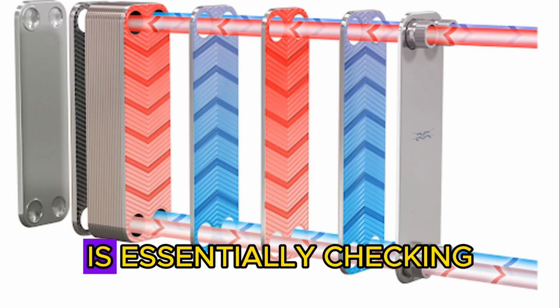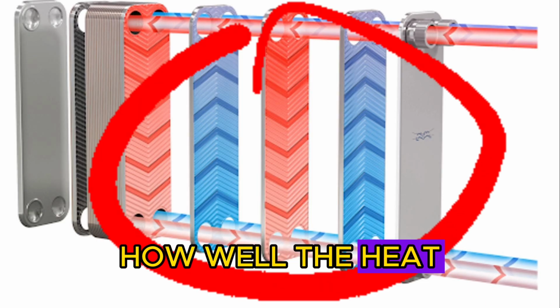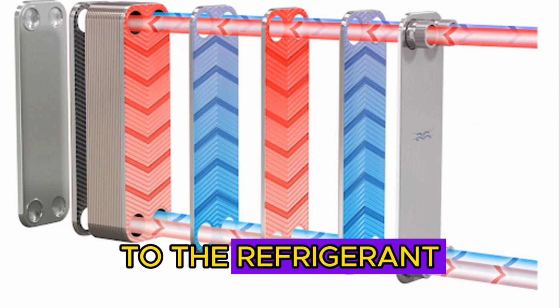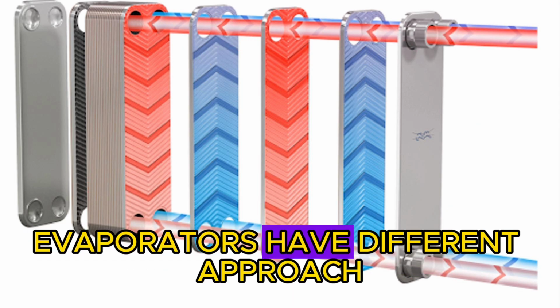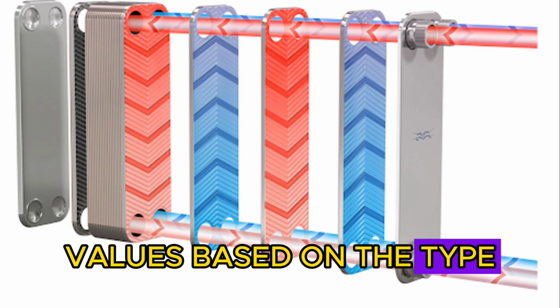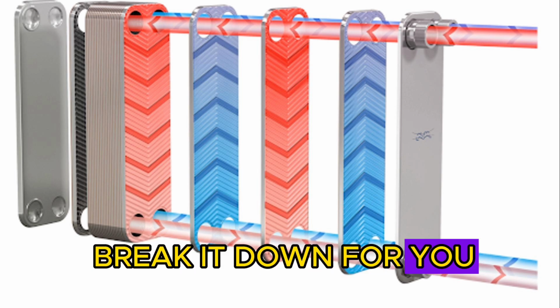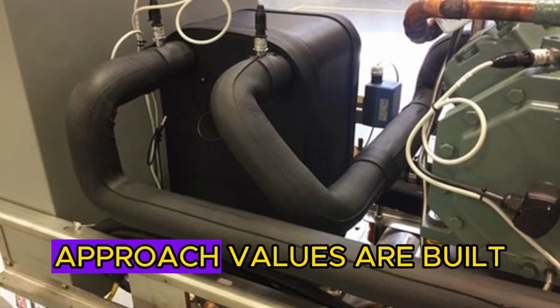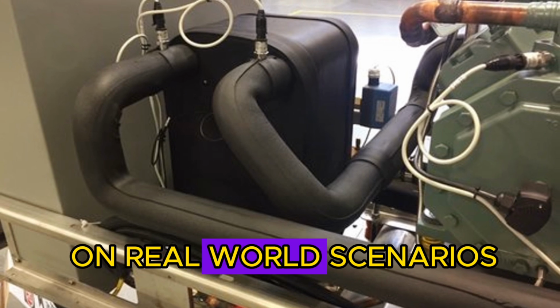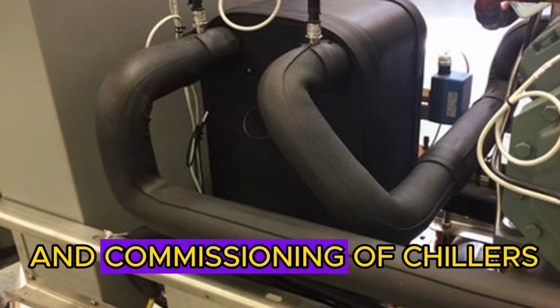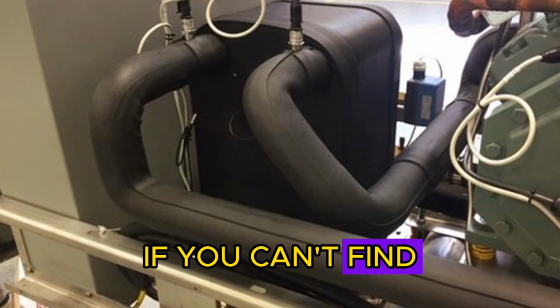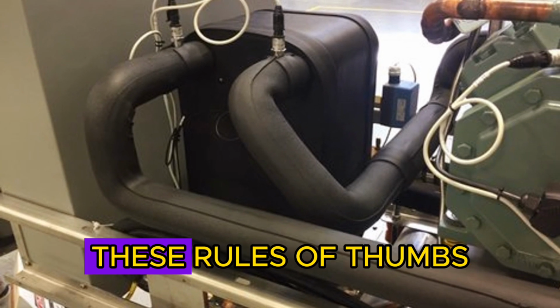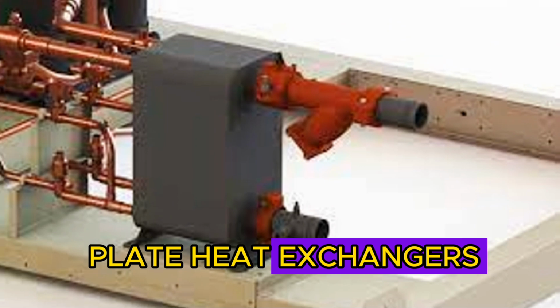What you're doing here is essentially checking how well the heat is transferring from the water to the refrigerant. Evaporators have different approach values based on the type, and we're going to break it down for you. All of the following approach values are built on real-world scenarios at the startup and commissioning of chillers. If you can't find the manufacturer's literature, these rules of thumb will serve you well. Starting with the brazed plate heat exchangers.